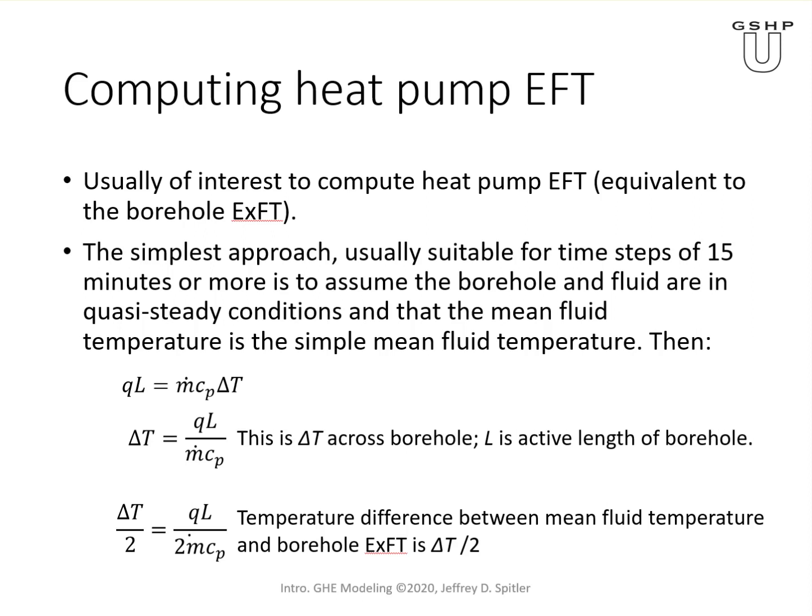What we usually want to know is the entering fluid temperature of the heat pump, or equivalently the borehole exiting fluid temperature. The simplest approach — which is suitable for time steps down to around 15 minutes — is to assume the borehole and fluid are both in quasi-steady state conditions, so the mean fluid temperature is just the simple mean. If you want shorter time steps, a more sophisticated approximation is needed, but for this introduction we'll use this simple approach.